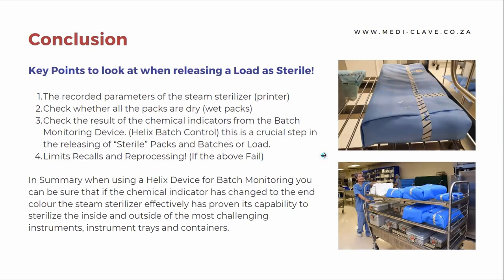And checking your batch control monitoring device is a crucial step in releasing your loads as sterile. If it shows a pass, then you can confidently release your load. However, if it shows a failure, you can reprocess your items in CSSD, knowing that it shows a fail before you've even sent them to theater. So it does limit recalls and reprocessing. In summary, when using a Helix device for batch monitoring, you can be sure that the chemical indicator has changed to the end color, and the steam sterilizer has effectively proven its capability to sterilize the inside and the outside of the most challenging instruments, instrument trays and containers.